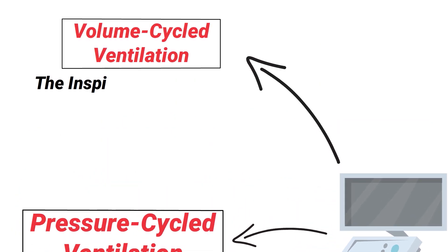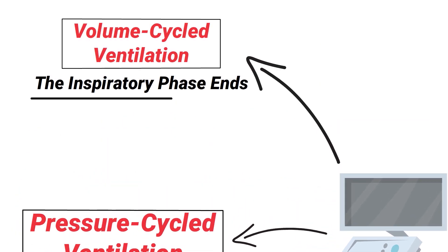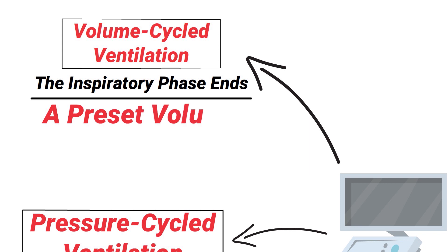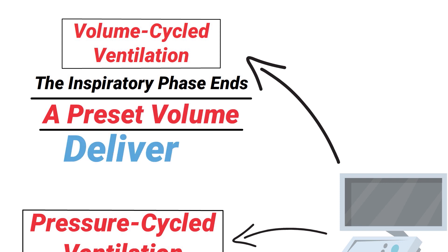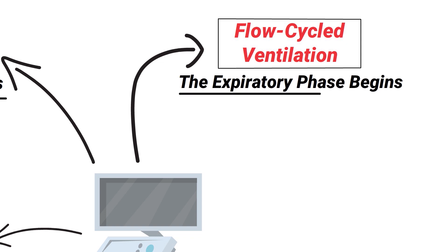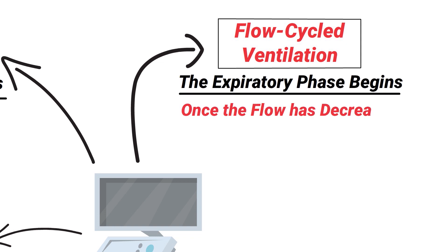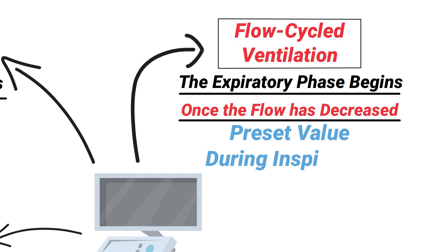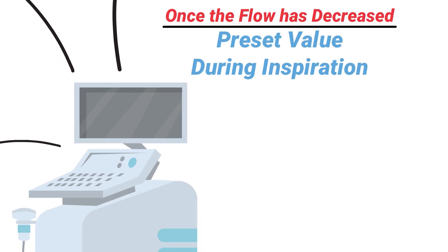During volume cycle ventilation, the inspiratory phase ends whenever a preset volume has been delivered. During flow cycle ventilation, the expiratory phase begins once the flow has decreased to a preset value during inspiration.